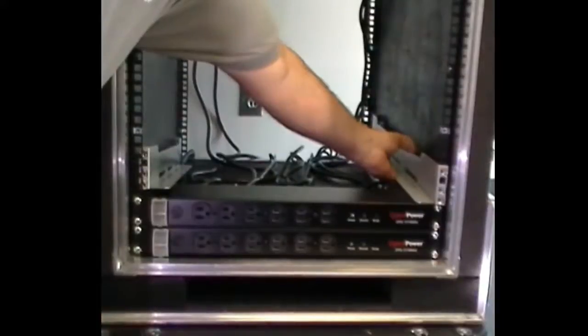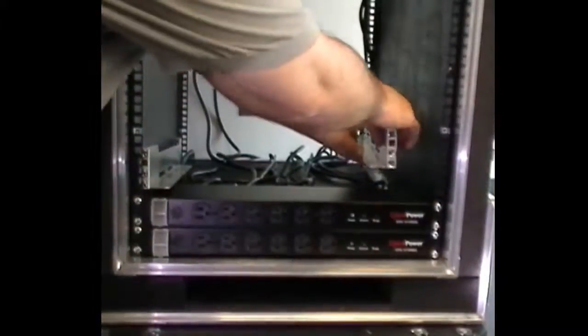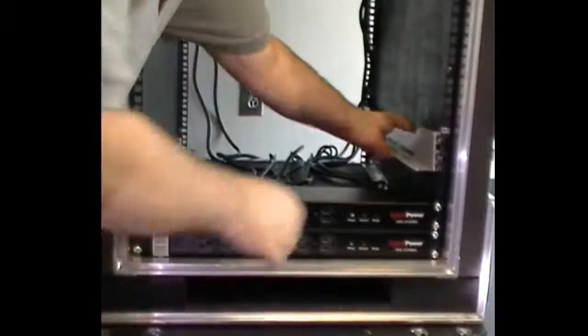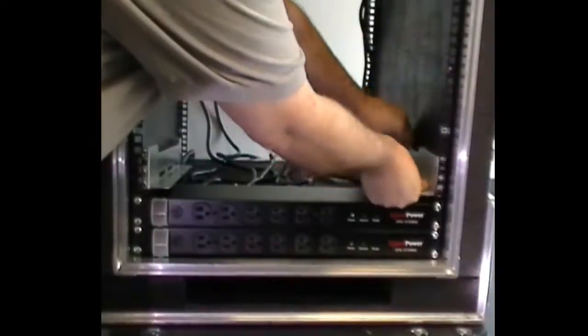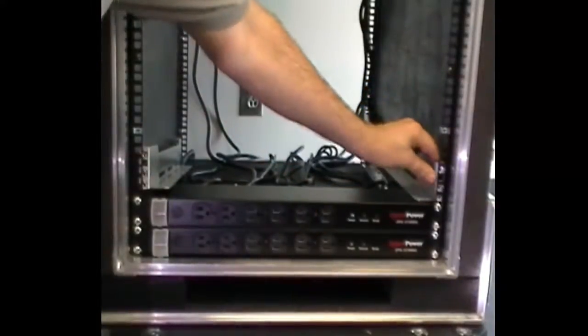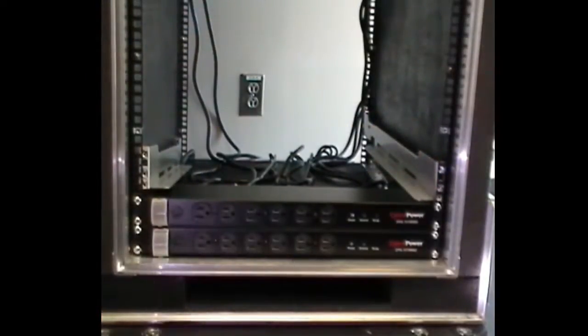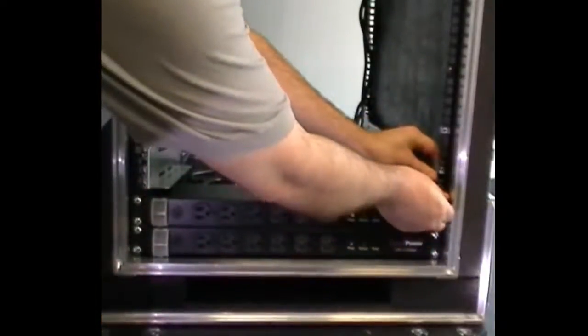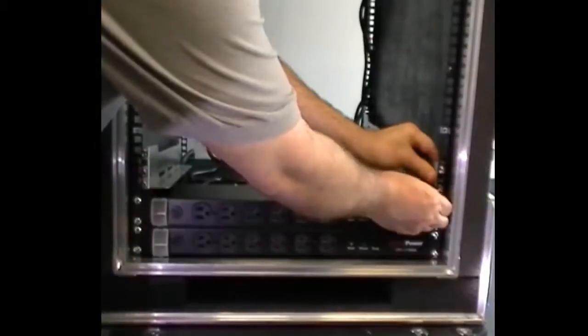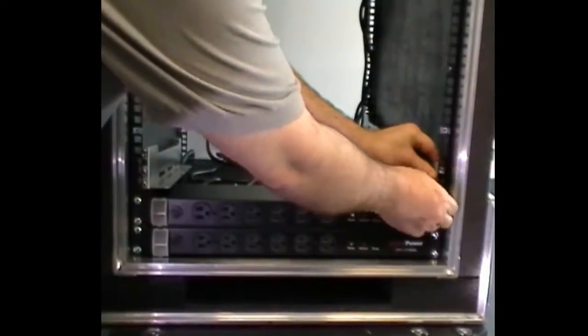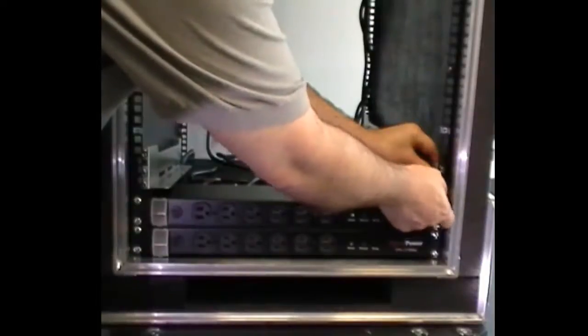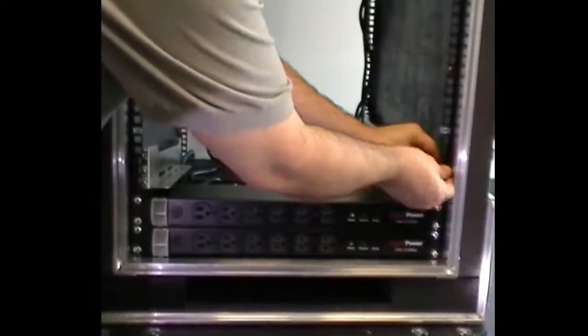Now we place the rail kits so they fit between the rails rather than outside the rails. Placing them outside the rails consumes a few millimeters of space, which is enough to make sliding components very difficult. Insert a screw into the bottom and top cage nuts, leaving the center cage nut free for securing the shelf or controller.